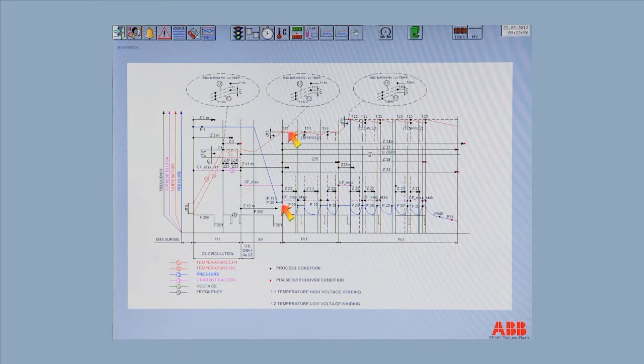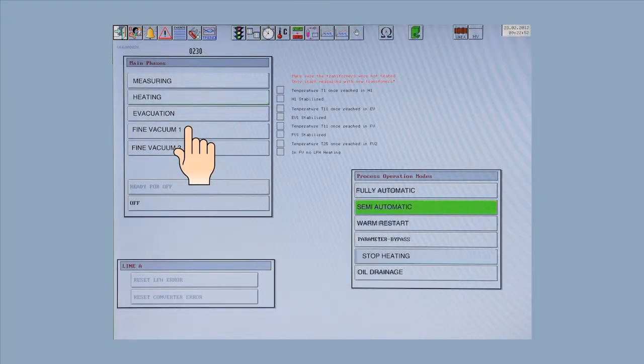When the temperature reaches the value defined by the temperature parameter T11 and the pressure reaches the pressure parameter P20, then the process can be manually advanced to the next step, that is, the Fine Vacuum 1 step.